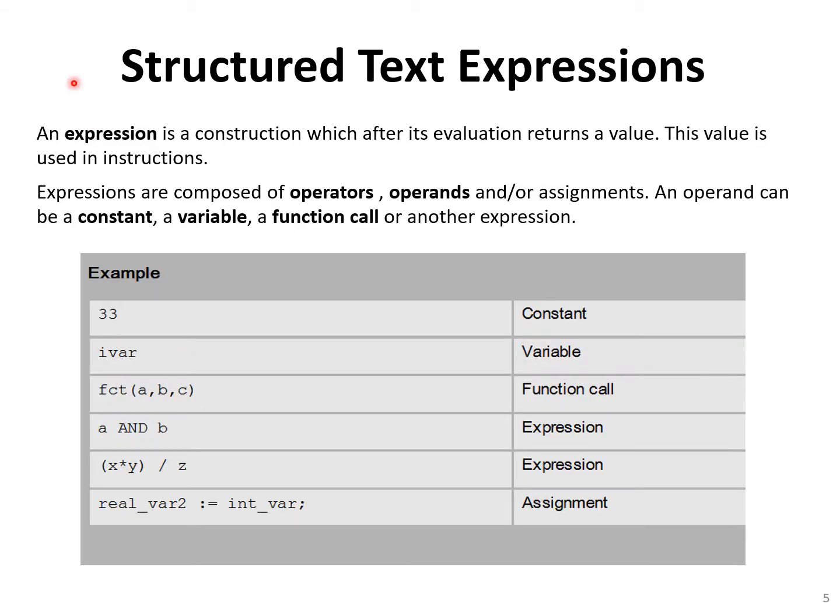Structured text expressions. An expression is a construction which, after its evaluation, returns a value. This value is used in instructions. Expressions are composed of operators, operands, and/or assignments. An operand can be a constant, a variable, a function call, or another expression.